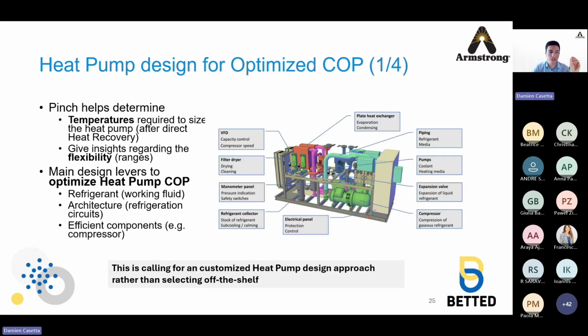And that's really it for the pinch. But then what's the next step? The next step is to find the right heat pump. Pinch helps determine the temperatures required for the heat pump and gives insight regarding the flexibility. So these are really the inputs that go into the heat pump design office. And then the heat pump design office has 3 main levers to optimize the heat pump efficiency. Remember, that's the COP. One is to select the right refrigerant. The other one is to design the right architecture within the refrigeration circuits. And the last one is to use efficient components, primarily the compressor.